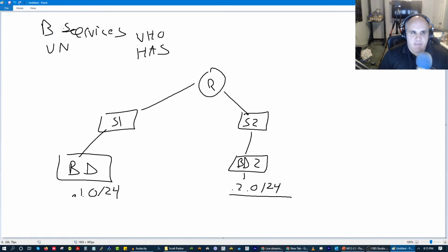So the first thing that happens, right, the BACnet device, when we do a discovery, it's going to send out the who is, and it's going to get an I am reply. And it's going to build a node list, right? It's going to build a list of BACnet devices. And those devices are really the IP address plus the device ID.